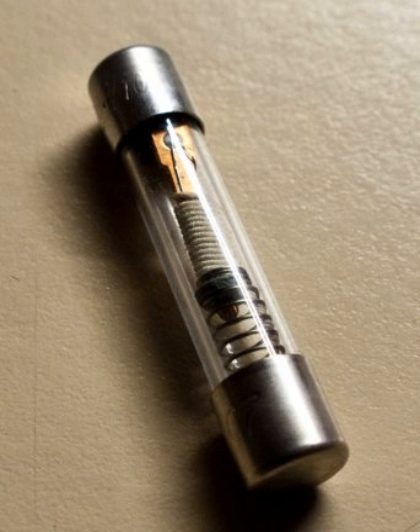Some fuses allow a special purpose micro switch or relay unit to be fixed to the fuse body. When the fuse element blows, the indicating pin extends to activate the micro switch or relay, which, in turn, triggers an event. Some fuses for medium voltage applications use two or three separate barrels and two or three fuse elements in parallel.